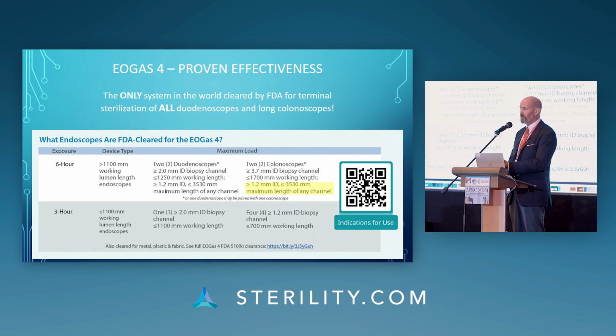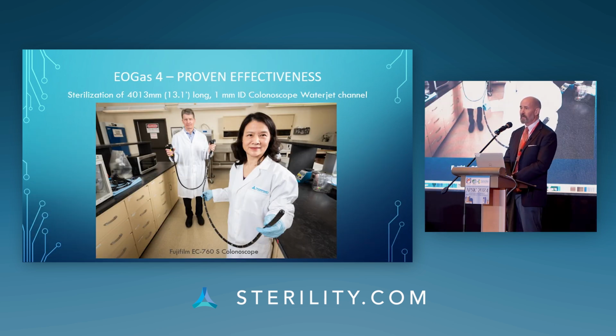And since we presented this information to FDA, we have presented additional information to the agency, and we have now shown that this system can sterilize a 4-meter lumen that is only 1 millimeter in diameter. You may ask, what scope has a 4-meter lumen to it? Well, this is a particular colonoscope with a very long water jet channel. And those of you that know colonoscopes, there are working channels. There's also a water jet channel that tends to be a good deal longer, and FDA requires that you demonstrate that you can sterilize this water jet channel to be able to get a sterilization claim. And there is no other process on the market that we are aware of that can sterilize a 4-meter, 1 millimeter in diameter lumen. This is over 13 feet.